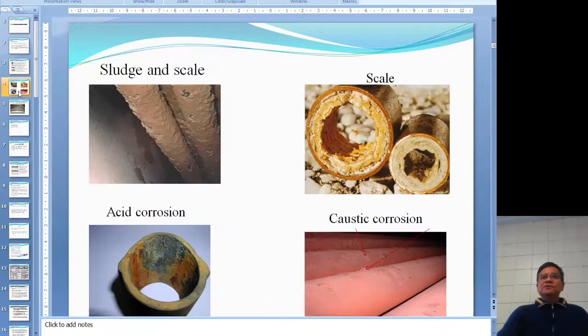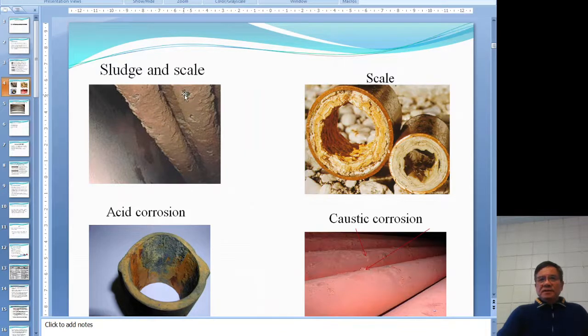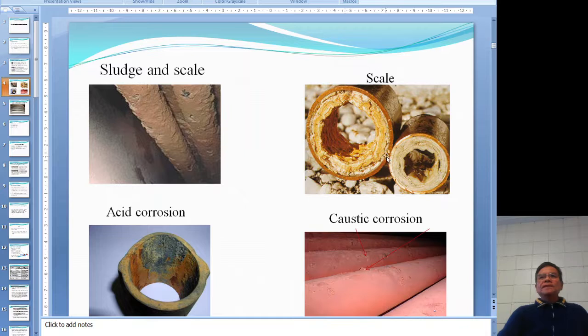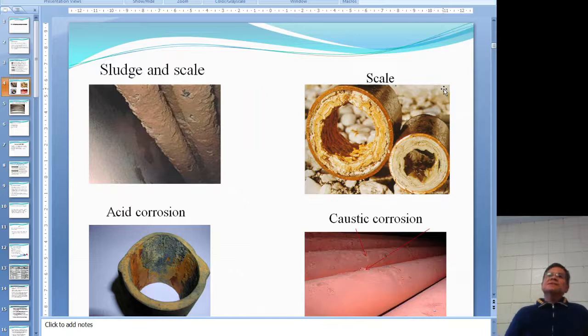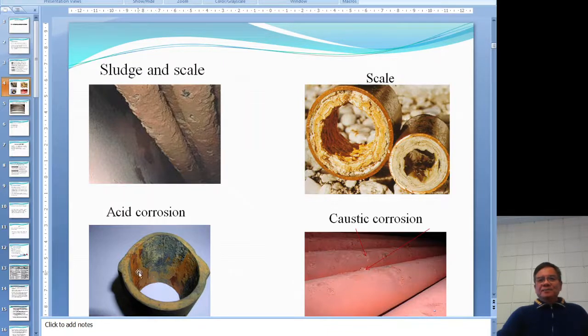Here are some pictures showing these problems. The outside soft layer is sludge, and the inside layer is corrosion. On the right-hand side you can see scale. In a really serious case, you can see almost half the pipe capacity is lost due to scale buildup inside. You can also see rust and black spots from corrosion on the tube.